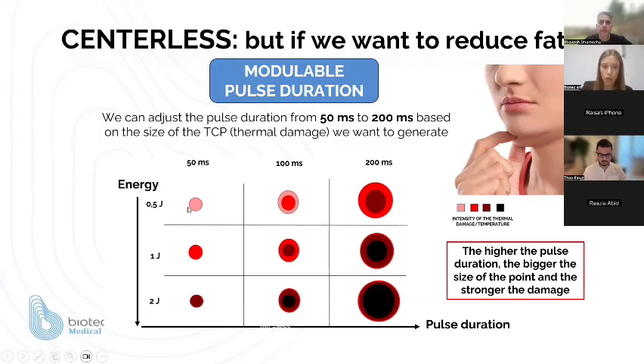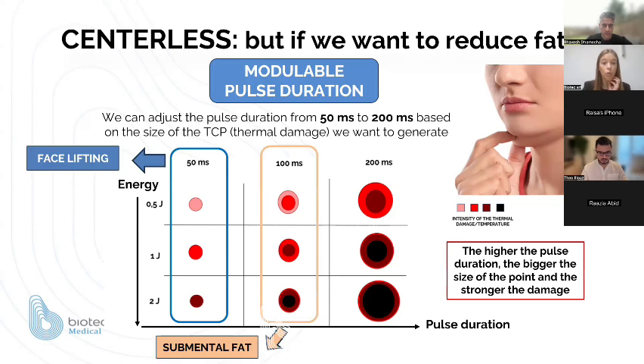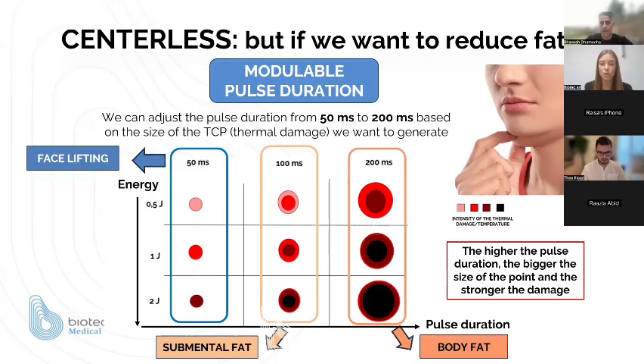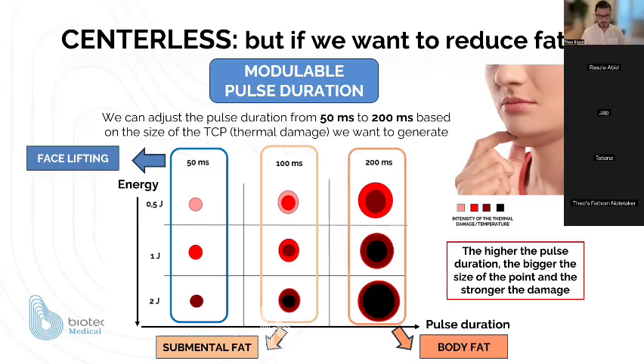So look at this table. You see that if we use 50 milliseconds, we have a small point, which is useful for the face where we don't want to reduce fat, but we only want a tightening effect. But if we want to reduce fat, what can we do? We can increase the pulse duration up to 75, 100 milliseconds. So we create a bigger point and we are also able to reduce fat, for example, on the double chin. So this is for the face, this is for submental fat, and 200 milliseconds, as you can imagine, is for body fat reduction.